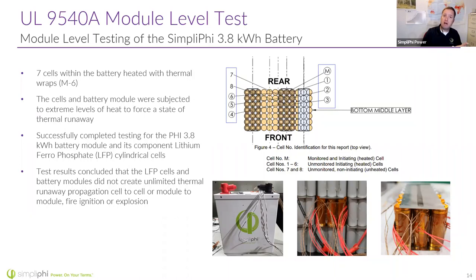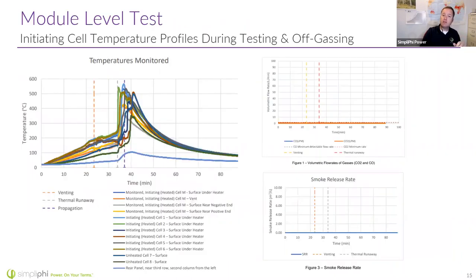So right now we're on the module level testing. This stuff is right out of our published test report. What we see here is as we're causing these batteries to go into venting, thermal runaway occurred, and the point is it drops off right after propagation and we return down to somewhat normal temperature ranges.